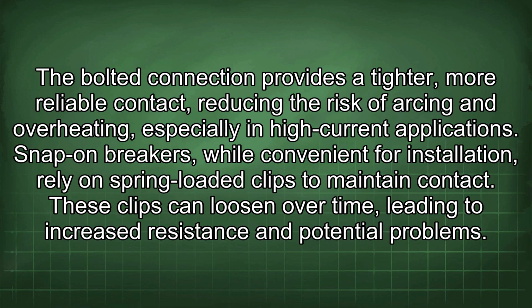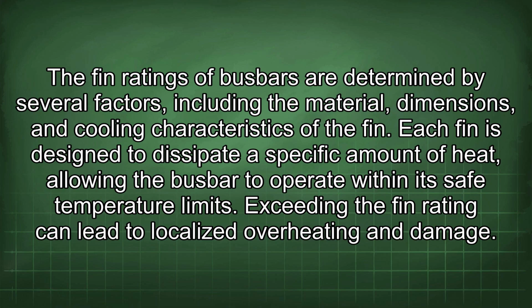These clips can loosen over time, leading to increased resistance and potential problems. The fin ratings of bus bars are determined by several factors, including the material, dimensions, and cooling characteristics of the fin. Each fin is designed to dissipate a specific amount of heat, allowing the bus bar to operate within its safe temperature limits. Exceeding the fin rating can lead to localized overheating and damage.